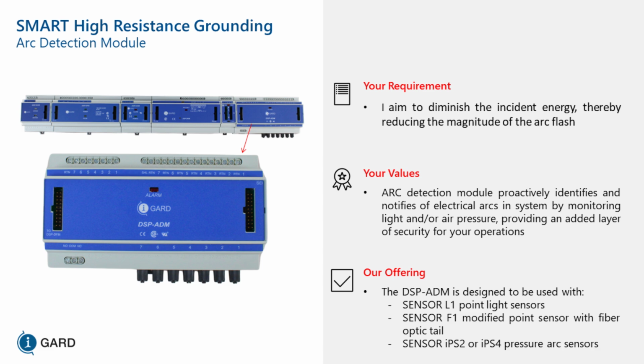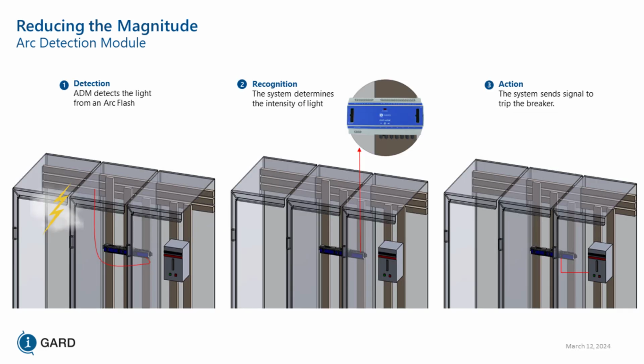So you can interlock your piece of equipment with light in order to have a check, shall we say, that you do have an arc flash. So not only do you have a smart HRG system that's telling you that you have minimized the risk of having an arc flash, we've also put in this relay to say, now you can reduce the energy in an arc flash and you can reduce the label. And we could do that because we're the only company that has the high resistance grounded systems. We manufacture the resistors and we manufacture the relays. So if you want something special, you come to us and we can probably do it.